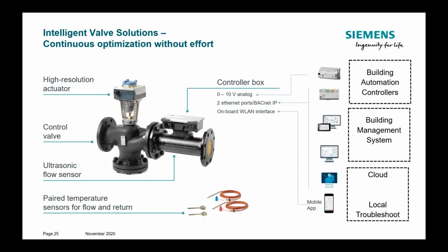And also, if a BMS is not available, an IP connection may allow us to connect into a cloud solution. This will save costs due to less system installation effort, and we have the trending and reporting in a cloud solution. In addition, with this intelligent and electronic solution, we have the capability to connect to this local device by a mobile app, as is today's technical standard. And there, for the local technicians, we have the capability to do online clear text alarming, and also to have guided, structured menus for troubleshooting, so that we have a guided troubleshooting.